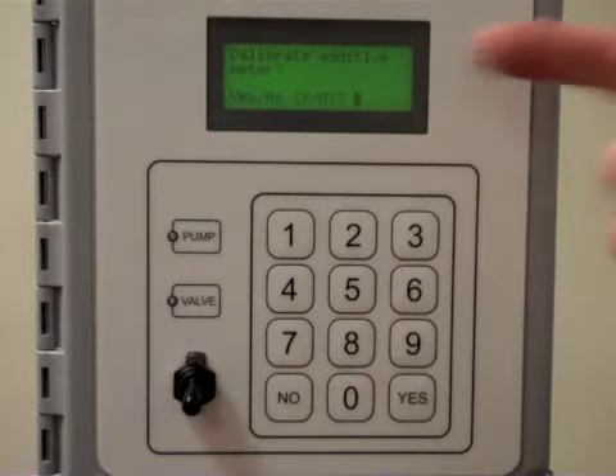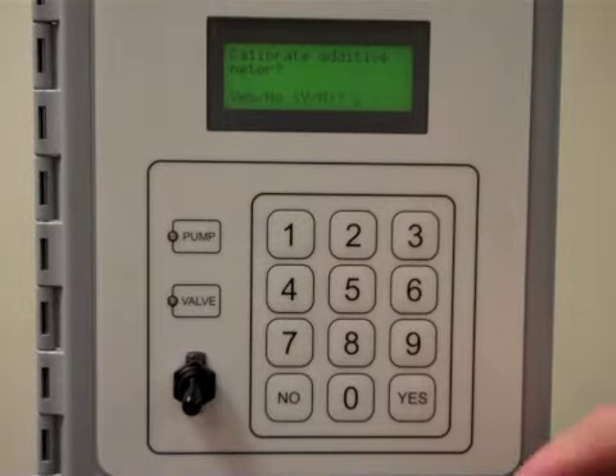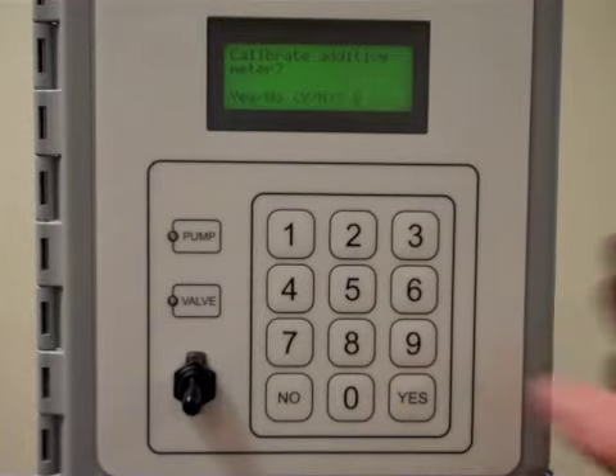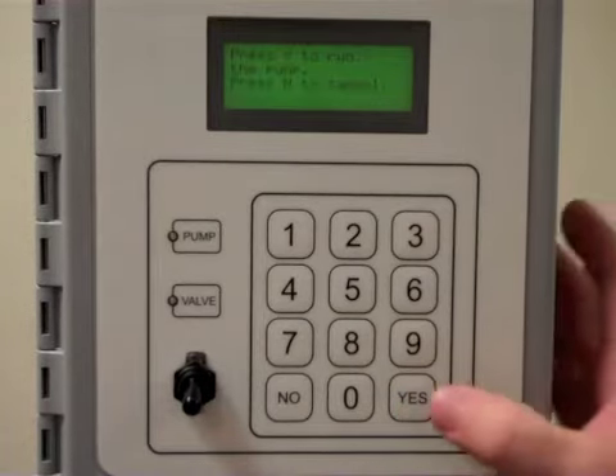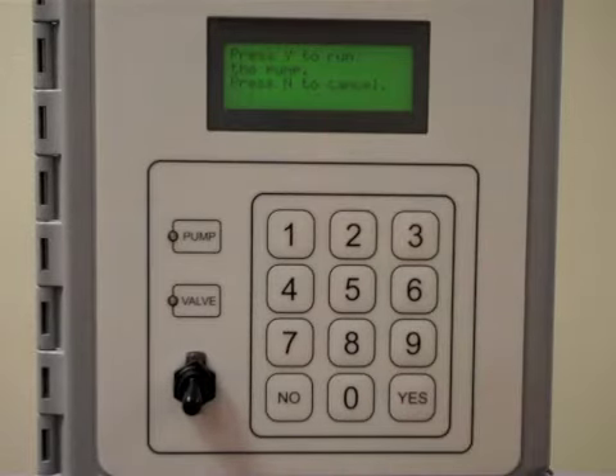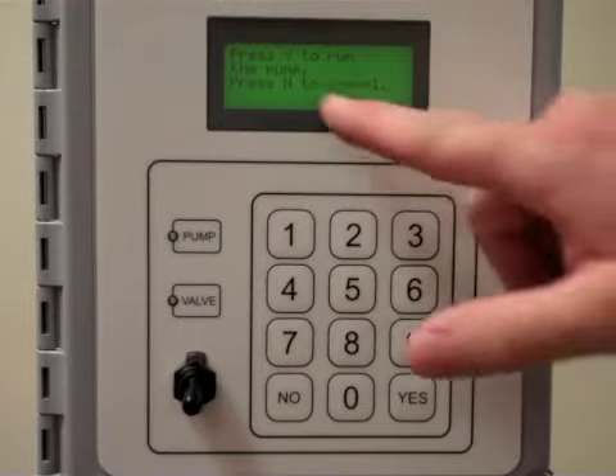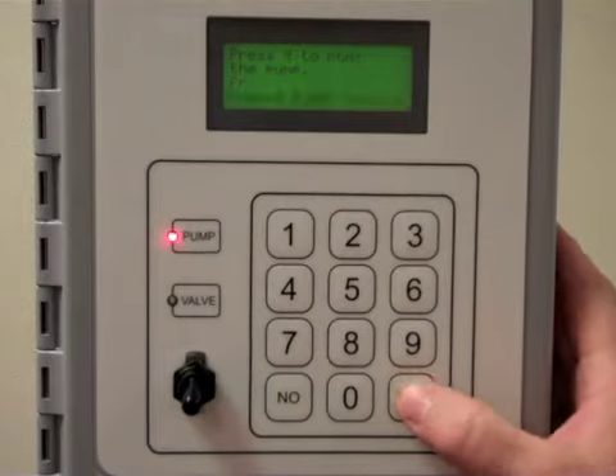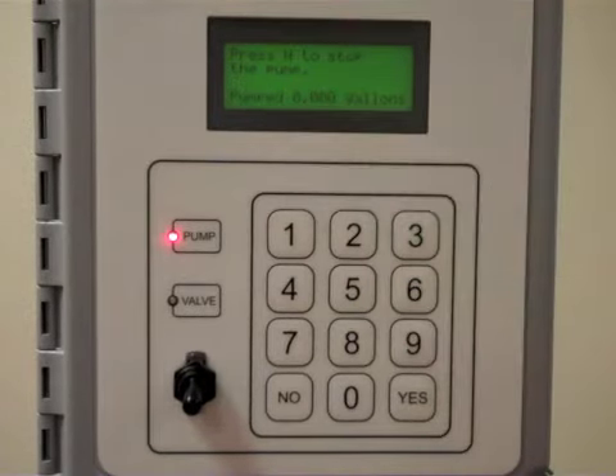Okay, now I'm at the calibrate additive meter option. That's what I'm going to do, so I'm going to say yes to that. So now when I press yes, the pump will begin to run. Then I can go dispense some additive into a container of a known quantity, say a 5-gallon or a 1-gallon, and then I'll come back in here. While I'm dispensing, you'll see on the front, I'm going to press yes now, and it'll show how much you've pumped. So we'll go do that now, and then we'll do the next step.